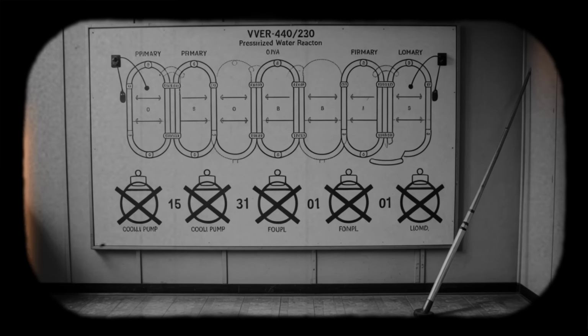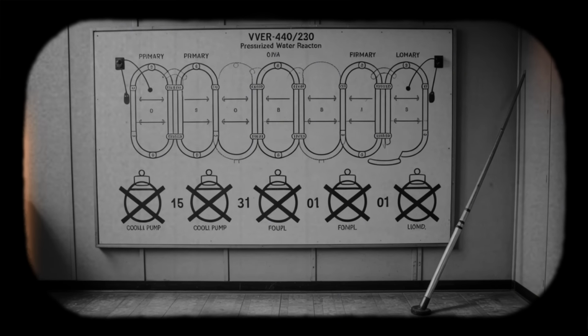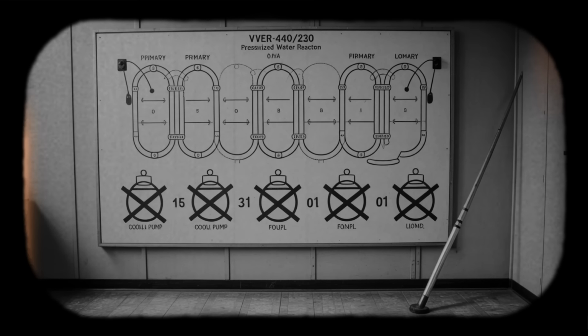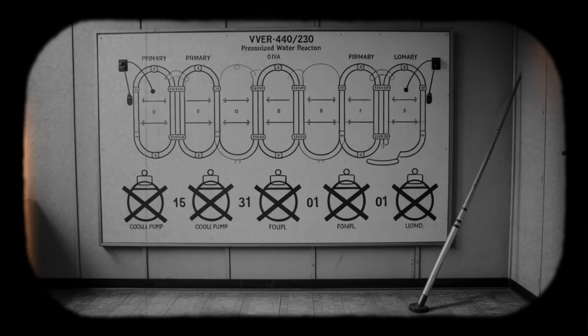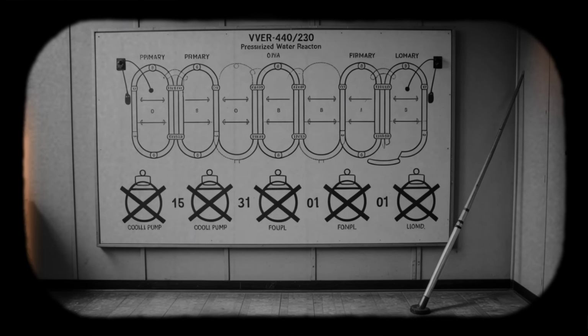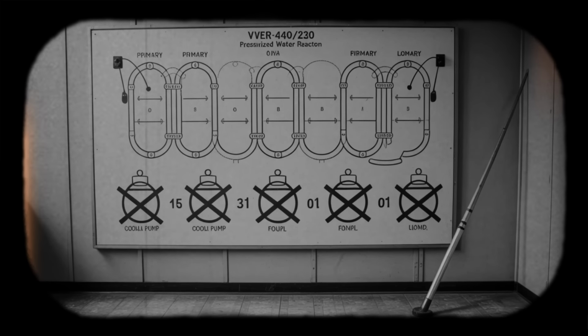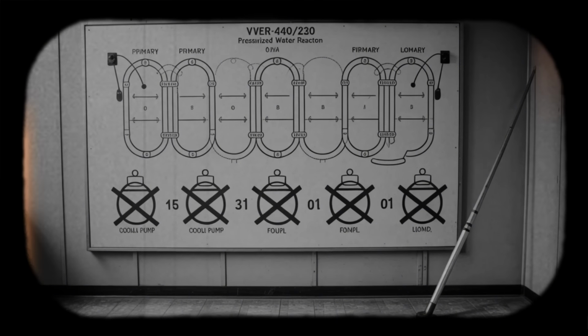These changes were not merely procedural. They required physical modifications: rerouting hundreds of cable runs, installing fire-resistant barriers, adding suppression systems, building new switchgear rooms or diesel generator bunkers. The cost was substantial. For older plants with limited remaining operational life, the economics favoured closure over upgrade.